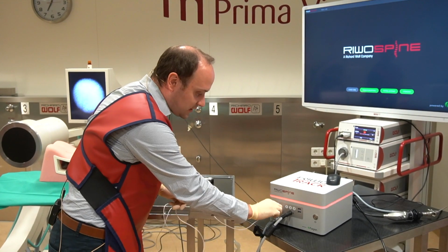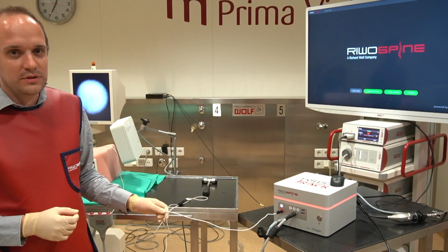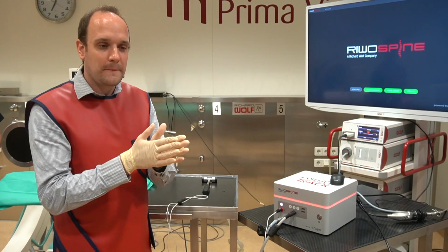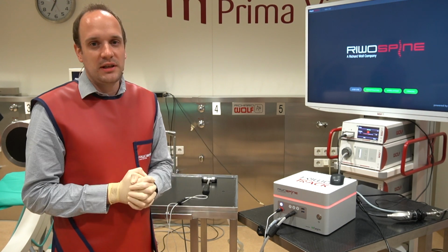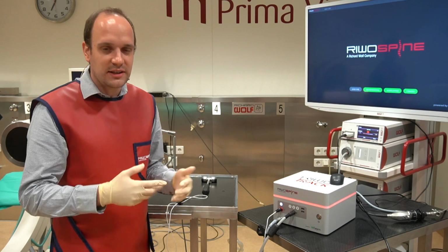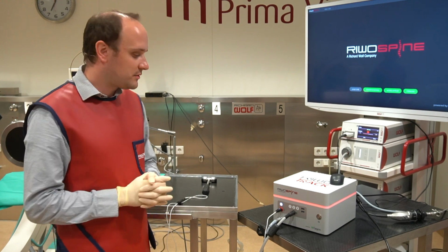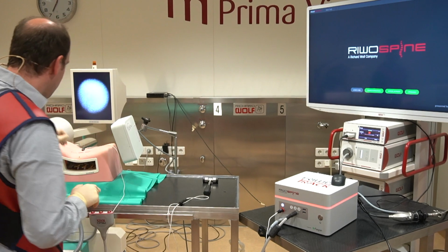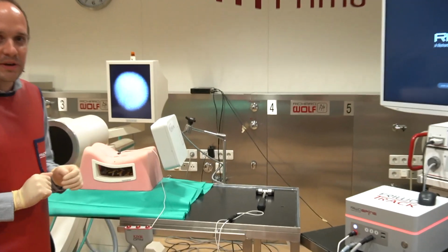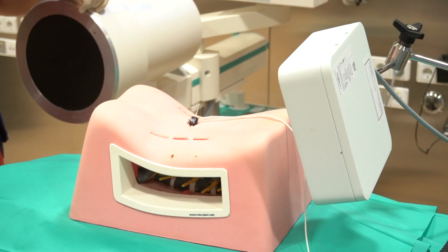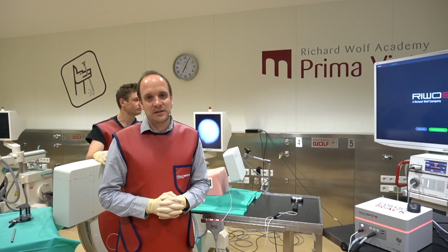To this port, the patient reference is connected. The purpose of the patient reference is to bring the position of the patient in relation to the X-ray images that we're going to shoot. You will understand later because we are going to reference the patient here live as well. This is fixed on the patient with a K-wire, in the spinous process, one level adjacent to the one we're working at. But the software will also guide us through all these steps. This is very important. The software explains to the surgeon every single step that has to be done.